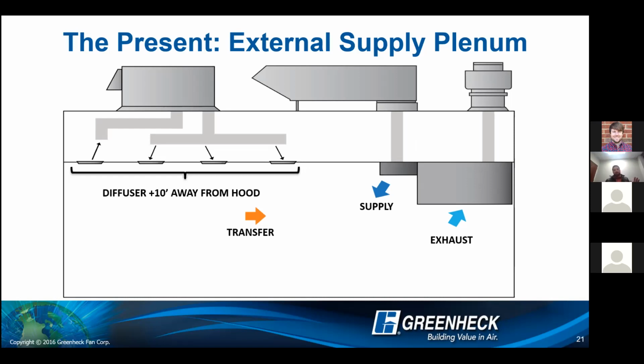Now, sometimes with these dedicated makeup air units, you will see a direct fire makeup air unit with a packaged DX cooling system. So then again, we're going to be cooling that air. But since we're not cooling it down for dehumidification, it can still be humid in that kitchen, but at least it's a little bit more comfortable. And then finally, with the present, you're making up the rest of your air through transfer air from your rooftop unit. And we touched on it already, but those would utilize diffusers, and we want them to be 10 feet away from the hood.